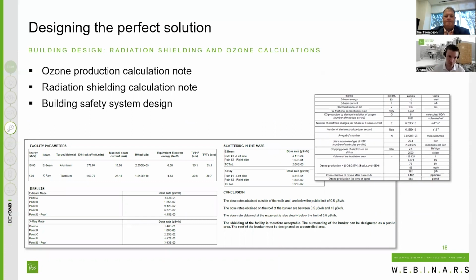We make calculation notes to show that the dose rate outside of the bunker is going to be below the limits accepted by the regulator. We also provide information about how much ozone production we'll have at full beam power, so we can help design the ozone extraction system and make sure it runs correctly once we start making beam.